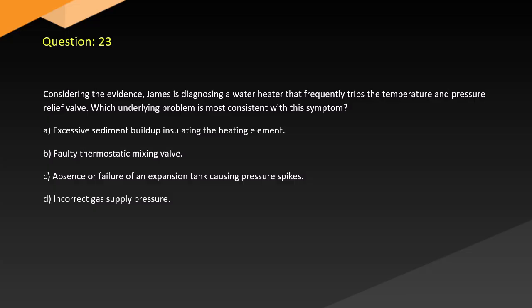Question 23. Considering the evidence, James is diagnosing a water heater that frequently trips the temperature and pressure relief valve. Which underlying problem is most consistent with this symptom? A. Excessive sediment buildup insulating the heating element. B. Faulty thermostatic mixing valve. C. Absence or failure of an expansion tank causing pressure spikes. D. Incorrect gas supply pressure.